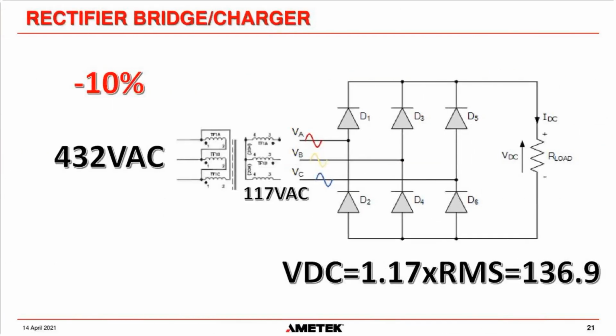But let's say we go down 10% and the input voltage is 432 volts. Our charger will still work - it's right at the limits of our tolerances, plus or minus 10% on the 480. So at 432 volts it will work. But if we just had diodes, look what happens on the secondary of this transformer using the direct ratios, 480 to 130: 432 would give us 117 on that transformer.